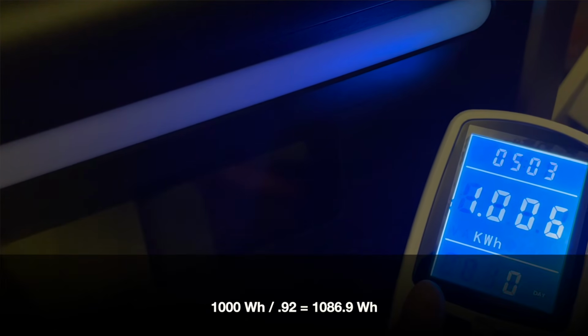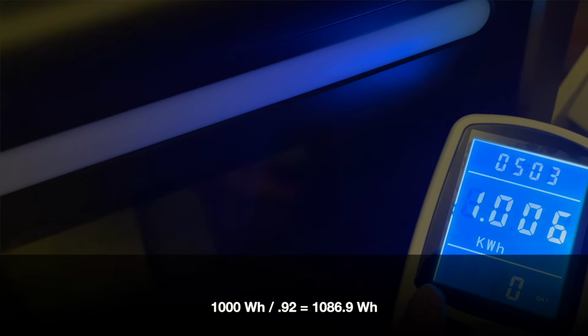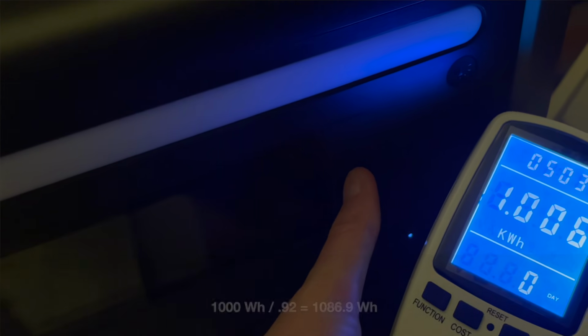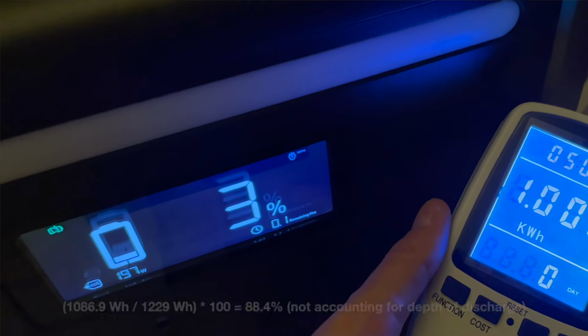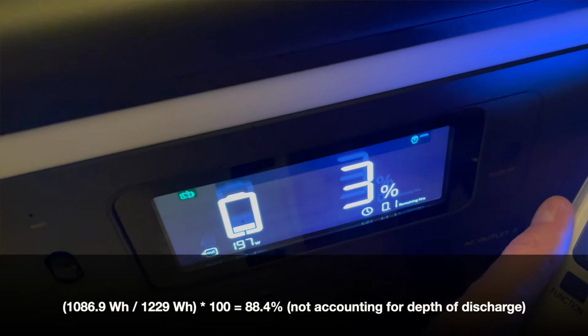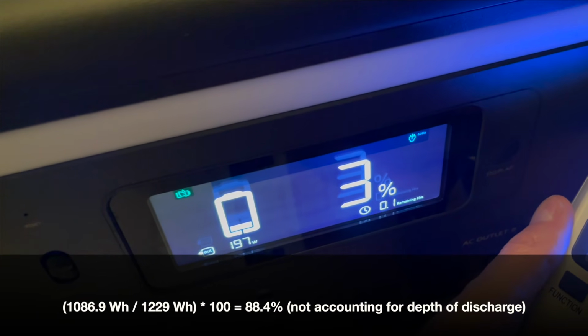With a lower power load, about 200 watts, purely resistive, that ran for close to 5 hours repeatedly. I got about 1,000 watt hours out of the unit, and dividing that again by 0.92 gets us to about 1,086 watt hours. Divide that by 1229, and we get to about 88% of the effective capacity of this unit.